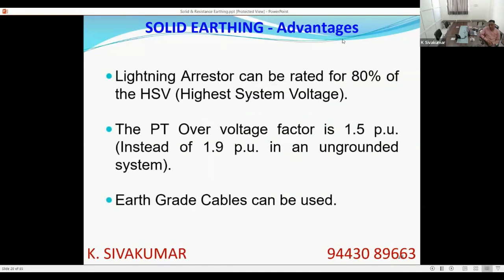And the lightning arrestor selection depends upon the method of system earthing. There is a factor in the formula for calculating the rated voltage of a lightning arrestor called the ground fault factor, or earth fault factor, or coefficient of earthing, which is 0.8 in the case of solid earthing. So the lightning arrestor can be rated highest system voltage into factor of earthing. So you can always go for a lesser rated voltage lightning arrestor; the cost and size will reduce.